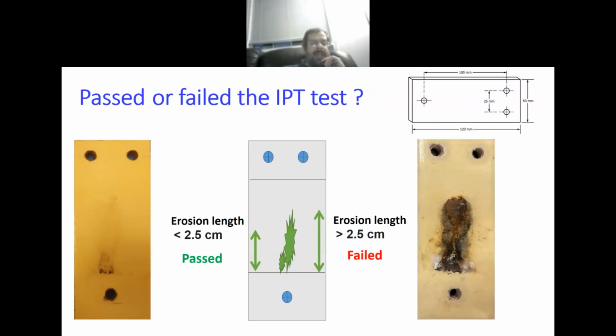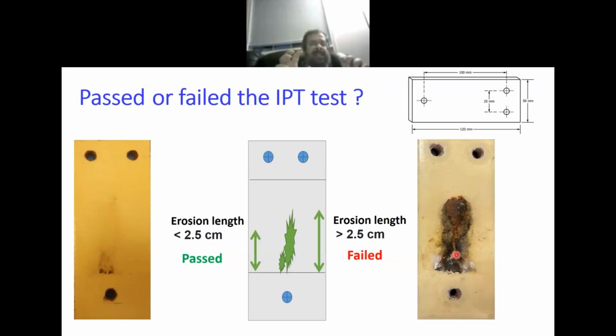Now, these are two samples. This one is the passed one, and the one to the right is the failed one. You can see some traces of tracking and erosion. Now, what is the criterion for pass and fail? If the length of this arcing from the ground end, which is this side, to the top is more than 2.5 centimeters, we consider the material failed. Or if there is a puncture in the material: sometimes we don't have this long erosion, but we have a concentrated arcing that leads to puncture of the material, so this material will fail. But if none of the above happens, then we consider the material passed and able to be adopted by the industry. This is the main test. We call it the material test, and it can be used to screen different designs of the materials. Next, please.